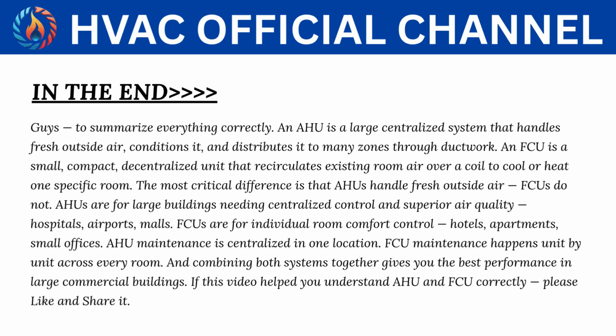In the end, guys, to summarize everything correctly, an AHU is a large centralized system that handles fresh outside air, conditions it, and distributes it to many zones through ductwork. An FCU is a small, compact, decentralized unit that recirculates existing room air over a coil to cool or heat one specific room. The most critical difference is that AHUs handle fresh outside air. FCUs do not. AHUs are for large buildings needing centralized control and superior air quality. Hospitals, airports, malls.